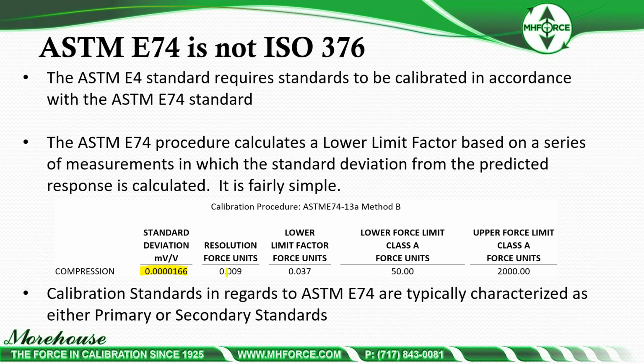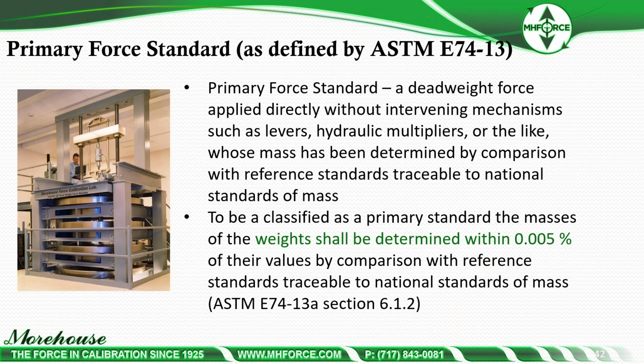We're going to rotate the instrument like we did in ISO. That's 0, 120, and 240 is recommended. We report the resolution, the lower limit factor, and then we assign a range. In this situation, it's just class A or double A, depending on what's going on. You can see you're not getting uncertainties, you're not getting anything else. You're basically getting an expected performance of that device when you go and use the same type of fixtures and everything else when you go and use that in your equipment or to calibrate a testing machine.